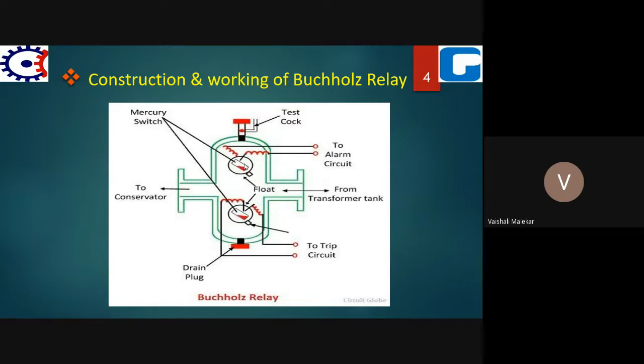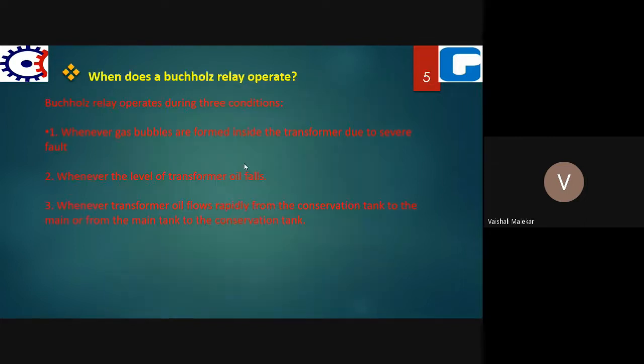So the Buchholz relay operates during three conditions. First, when gas bubbles are formed inside the transformer due to a fault, this relay will operate. Second, when the transformer oil level falls, the Buchholz relay will also operate. And third, when transformer oil flows rapidly from the conservator tank to the main tank, or from the main tank to the conservator tank. So in these three conditions the Buchholz relay will operate.